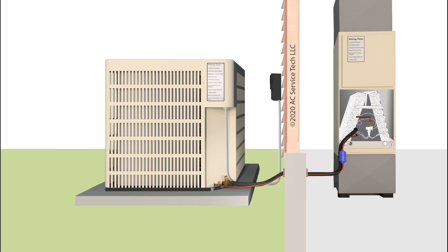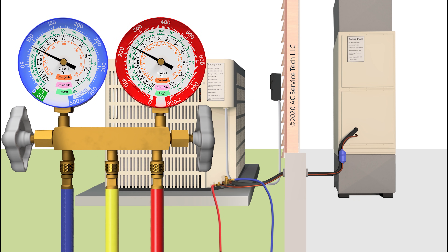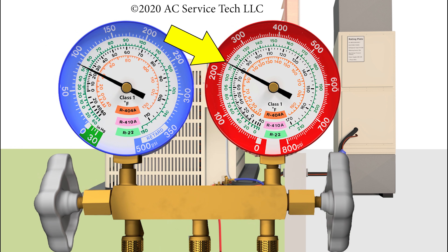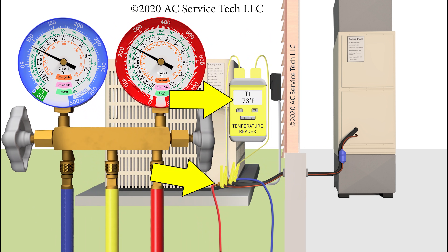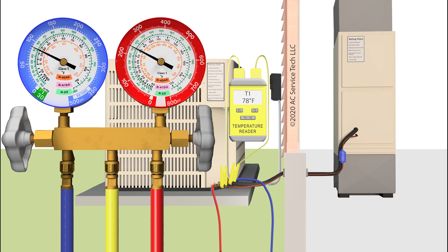When you arrive at the site and the evaporator coil is still frozen at the indoor unit, you can hook up your gauges and continue to let that run and check your subcooling. You're also going to need to know what refrigerant's in the unit — in this instance it's R-410A. On our red gauge we read 235 PSIG. If we bring that into the saturated temperature on the inner ring for R-410A, we read 80 degrees.